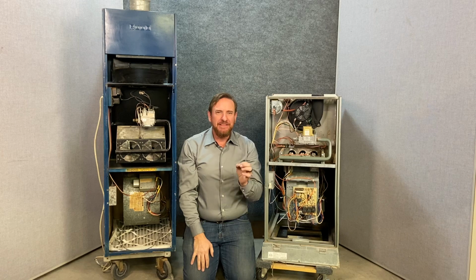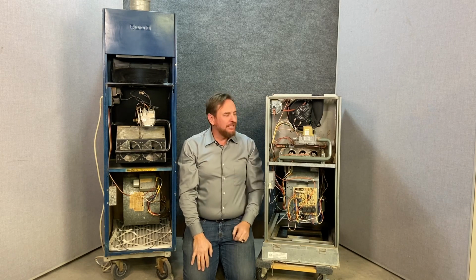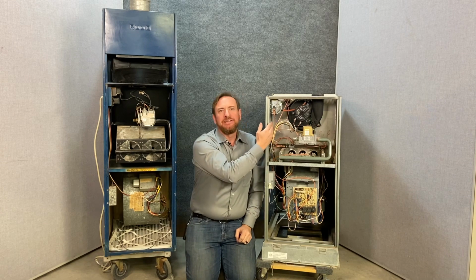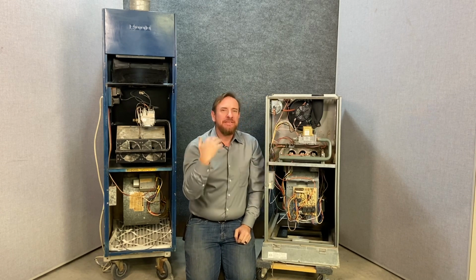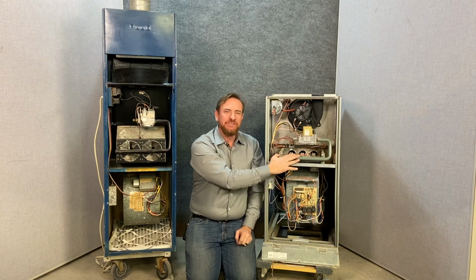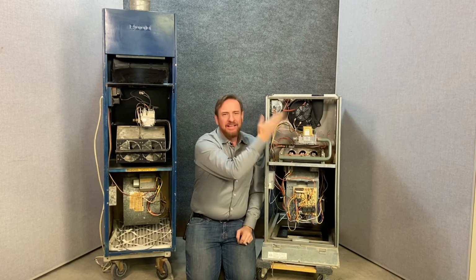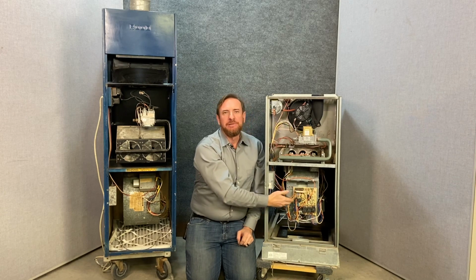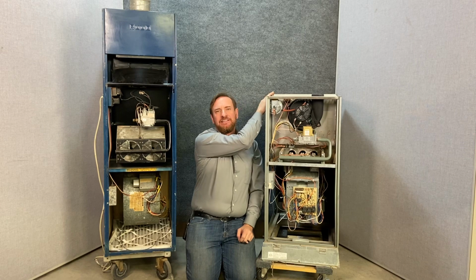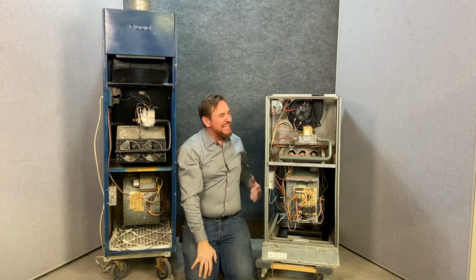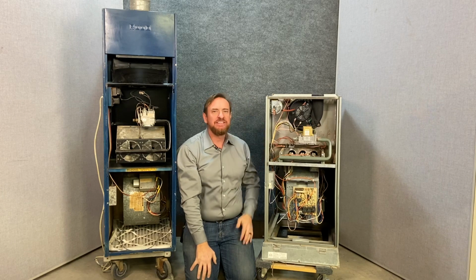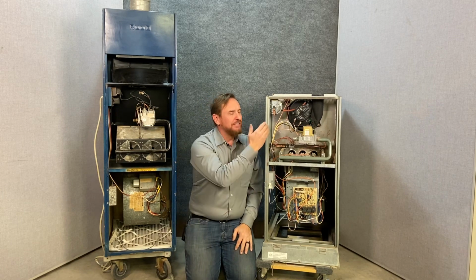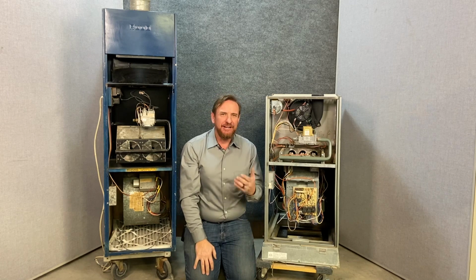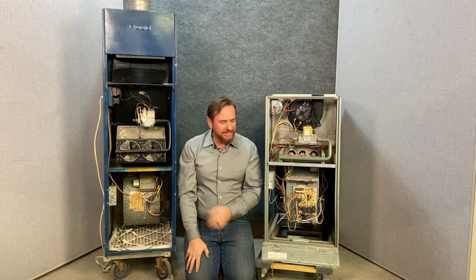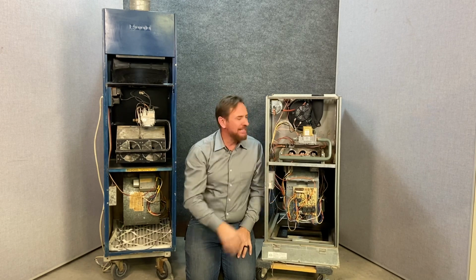Now, while we're talking about the limit switches, if a primary limit switch fails, you need to be thinking first, airflow, airflow, airflow. A lot of students, when they get into class, think, whoa, the primary limit, it's getting too hot, and they think the gas side. But you need to be thinking the airflow side. The gas is going to be already set for us. So if that primary limit's failing, what's happening on the airflow? Is that filter dirty? Is this blower in the right speed? Is it moving enough air? Is the evaporator coil above it clean, or is it dirty, restricting airflow? Are there too many vents closed? Anything with airflow, you're not moving enough air across that heat exchanger to keep it cool, so to speak. So when a limit switch trips on any system, you need to be thinking airflow, airflow, airflow. So very simple process, whereas this one has the control board monitoring every single aspect of the system.